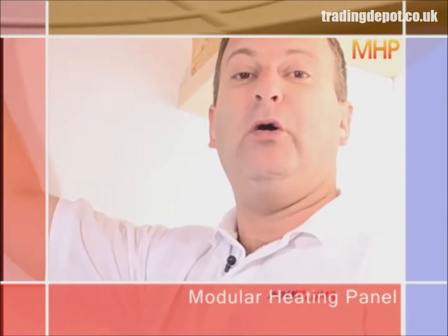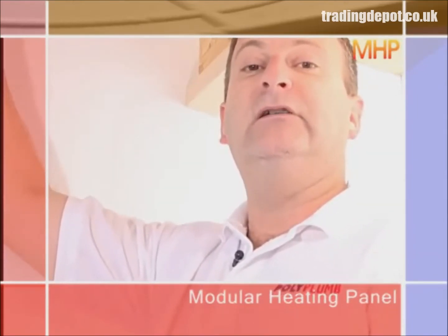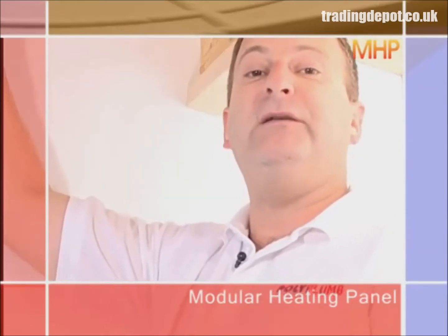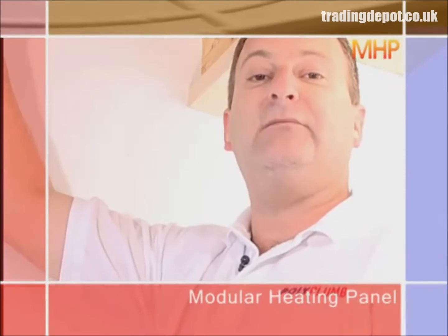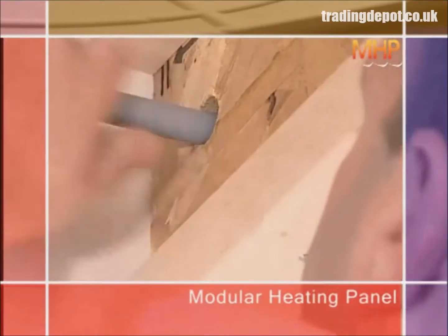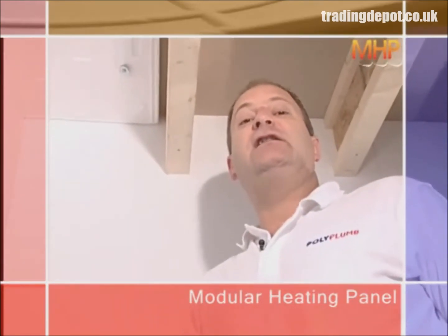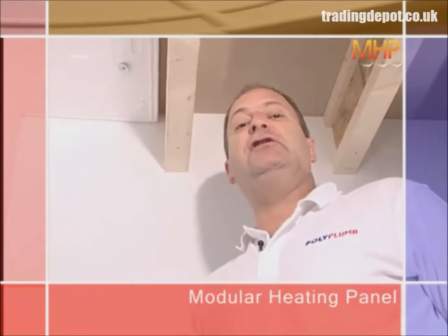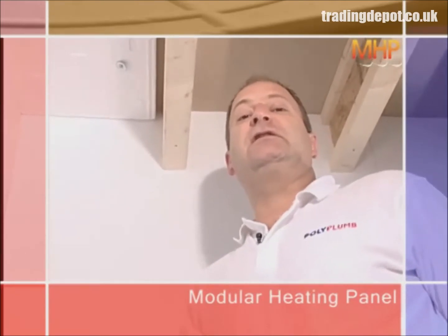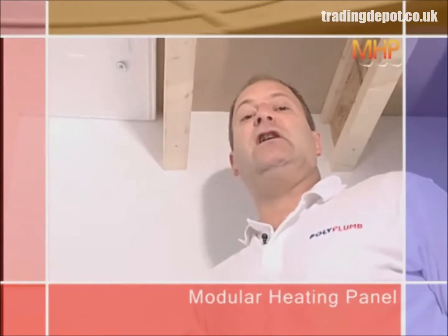Modular heating panels can be installed from above or below. In this example, we're showing an installation below an in-situ new build floor. The first thing to do is to put the 15mm Polyplumb flow and return pipes in, which will later connect to the modular heating panels. The panels are then simply placed between the joists on the underside of the floor and screwed into position using screws and washers, avoiding where the pipe runs are.